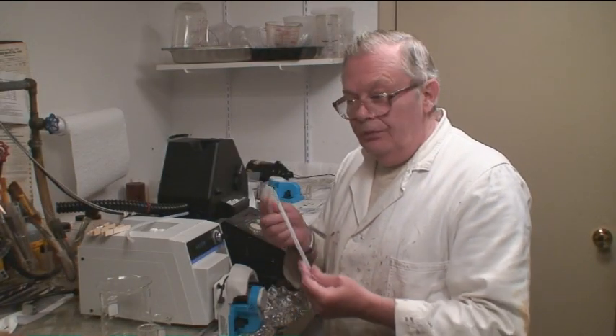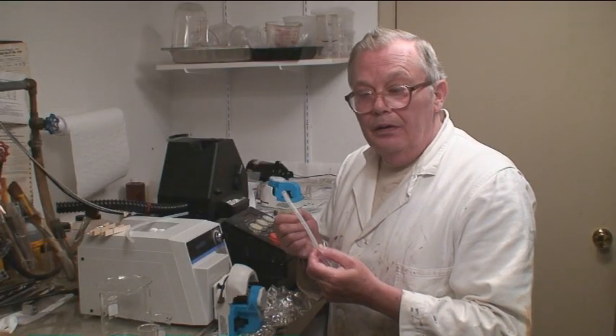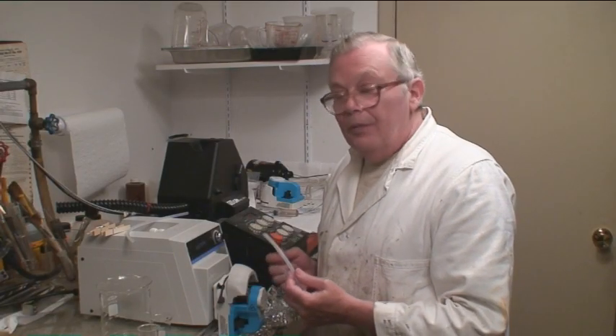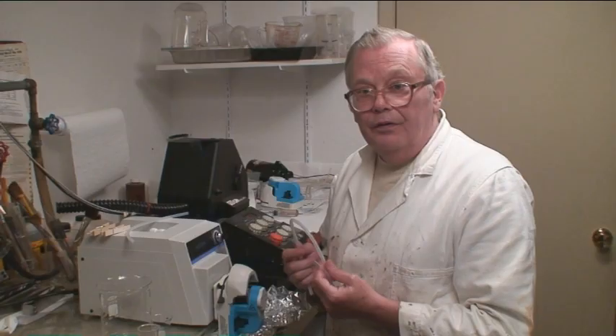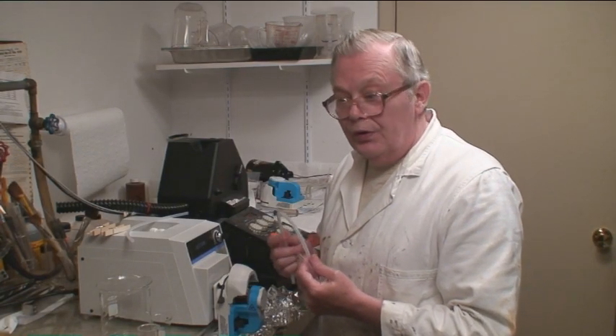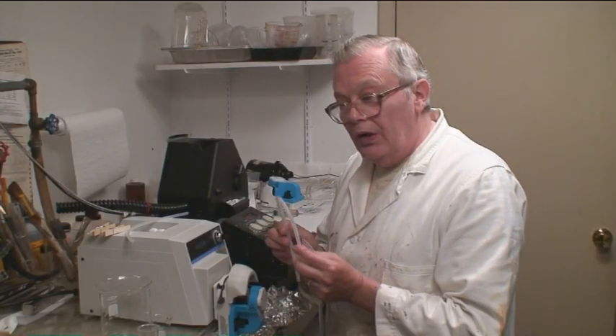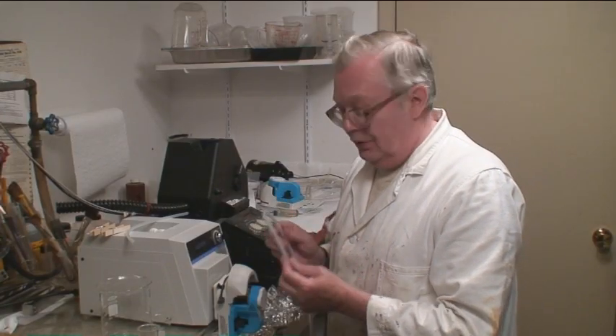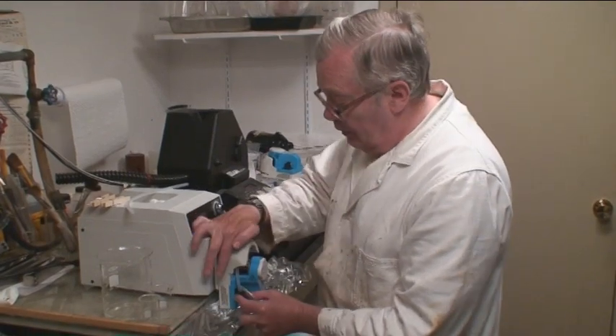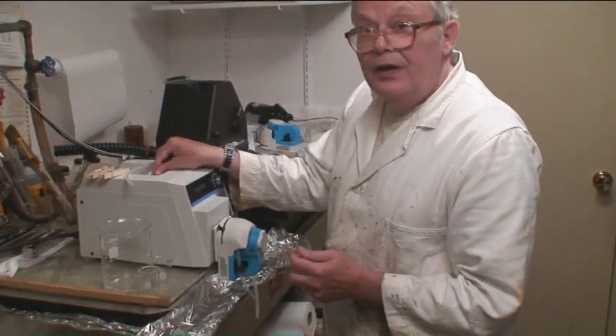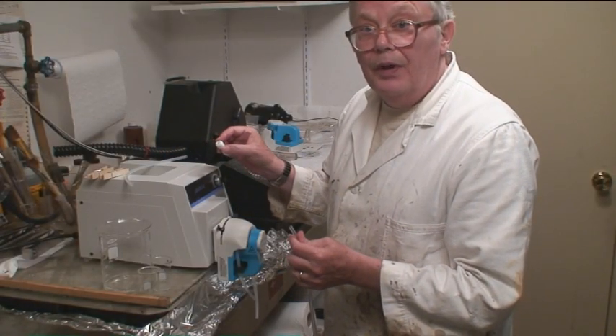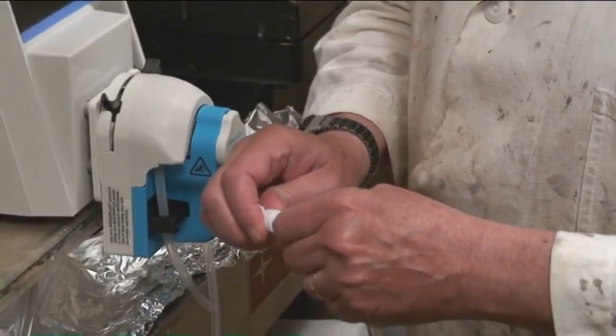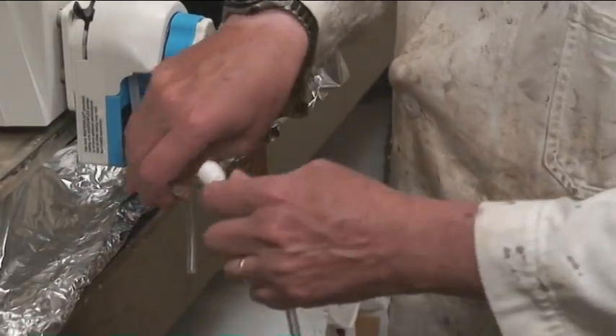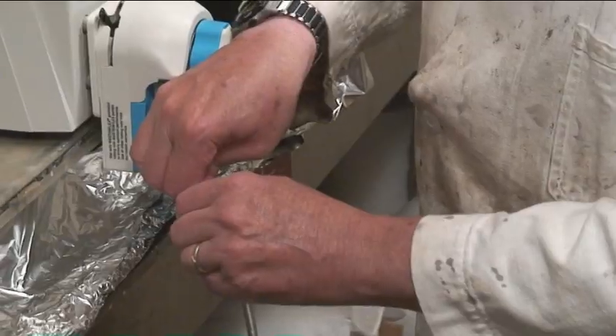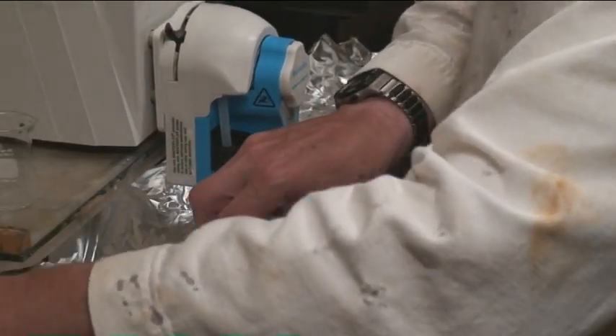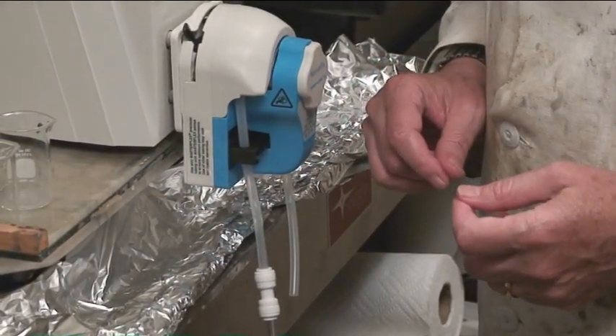I've told you about the need to use specially compressible tubing for a peristaltic pump. The problem is that this tubing is extremely expensive. So in order to conserve on your expenses, one of the things you can do is to put a short length of compressible tubing into the unit, as I demonstrated before, lock it in place, and then splice it to the less expensive non-compressible tubing. The compression fittings, as you saw in some other portions, are very, very reliable and are leak-free, and they simply snap in. And then you can place the non-compressible tubing into your solution or into your reactor.